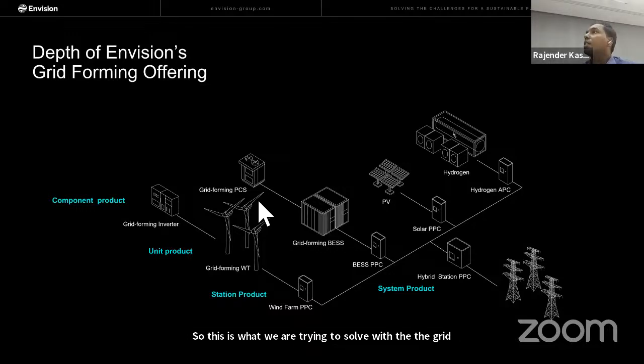So when the grid forming PCS is connected with the BESS system, the grid forming PCS can offer a synthetic inertia that can mimic the physical inertial response provided by a synchronous machine. During a frequency disturbance, a voltage angle difference occurs between the voltage of the grid forming inverter and the network voltage waveform. So the gap can be instantaneously compensated by injecting or absorbing current from the PCS. This can be done without much measurement or control response, so it will act to balance supply and demand, as well as restore the frequency levels.